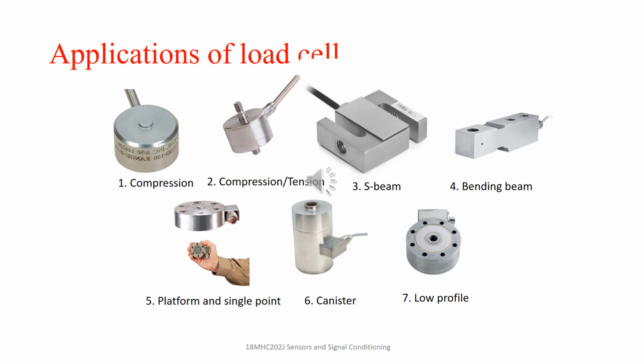The fifth type is the platform and single point load cell. It is used for commercial and industrial weighing systems. They provide accurate readings. Next is the canister type. This is used for single and multi-weighing applications, with a stainless steel design and sealed for wet areas.